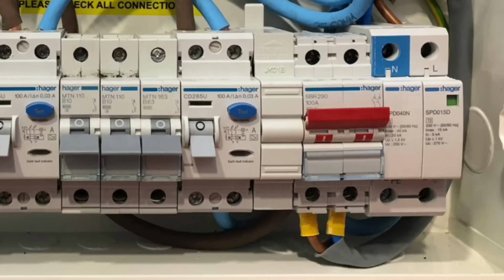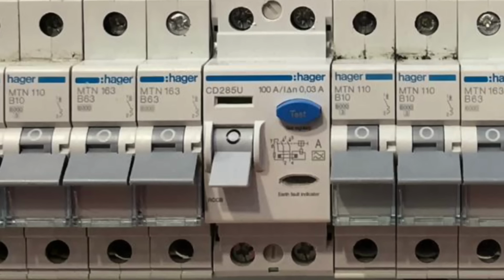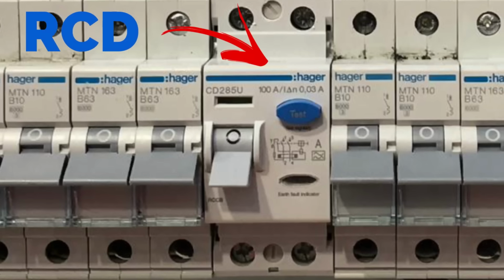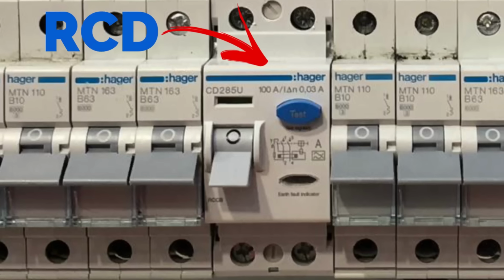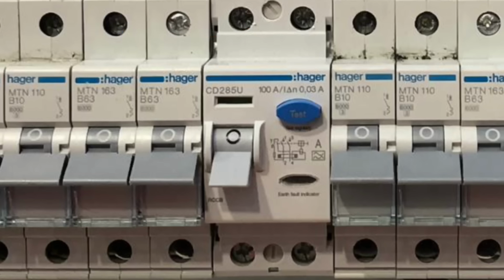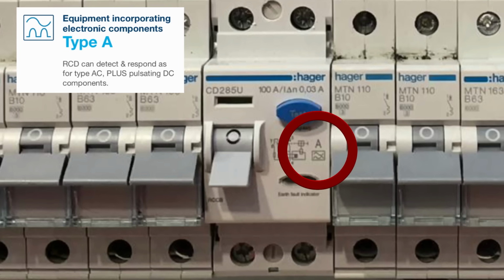So Paul, another really great thing about this consumer unit that we're looking at here, as we said, we're calling this an 18th edition board. We've got the surge protection built in. But what's the advantage as well with this RCD? What have we got going on here? The 18th edition brought in two requirements for the RCD in a split load consumer unit like this one. The installer must take account of, or have knowledge of, the type of loads connected from the RCD. We know now that a lot of electronic equipment fed in a standard house can generate pulsating DC faults or residual currents. So you will notice the RCD is now Type A, which is a specific type that can detect these pulsating DC, as well as AC type RCDs.